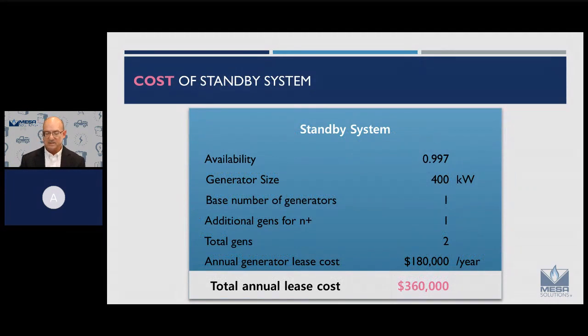The standby system, suppose the individual availability of a generator is 0.997. In this example, we're just looking at like a 400 kW generator. For the load, maybe we just need one generator and perhaps we want to have an N+1, so there's two total generators. Just using notional numbers, suppose the cost to lease one of those generators is $180,000 per year, so your total lease cost would be $360,000.